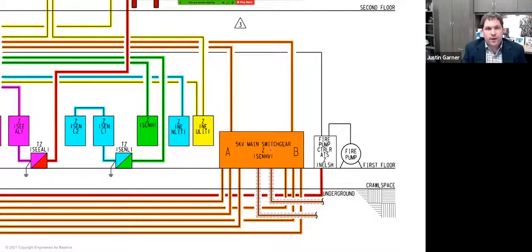Depending on where you are and the utility company in your area, this could be all the way up to 15,000 volts or even more. But normally you're going to see somewhere in the range of 4160 up to 15,000 volts coming in in this type of scenario. It's important to note that a medium voltage system is anything between 1,000 volts and 100,000 volts. So normally you're not going to see high voltage, which would be that next level up, as a direct feeder into a commercial facility. Industrial, yes, you might see that, but not in a commercial facility.